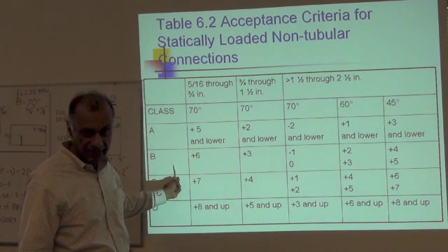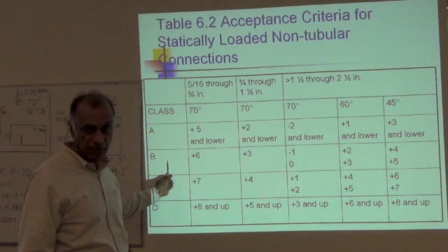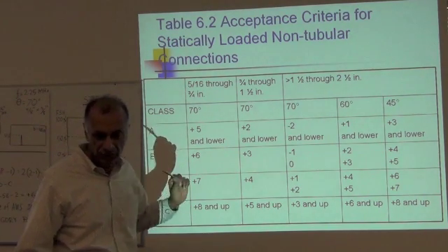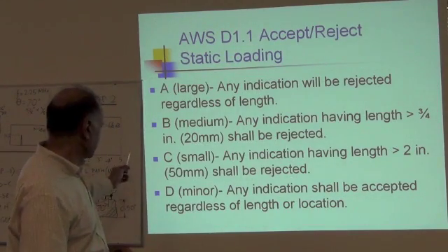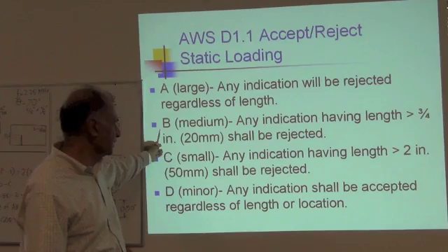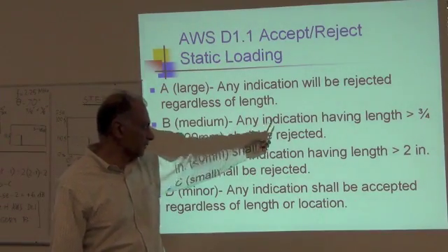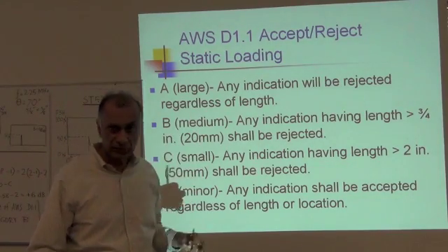Now we have to go to the next slide to find out if class B is acceptable or rejectable. In the next slide, indication class B is a medium indication, which means that any indication having a size that exceeds 3/4 of an inch shall be rejected.